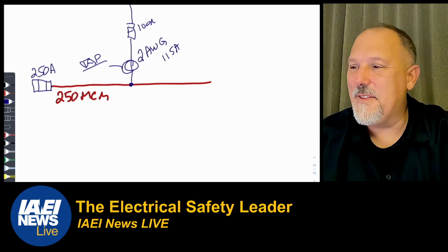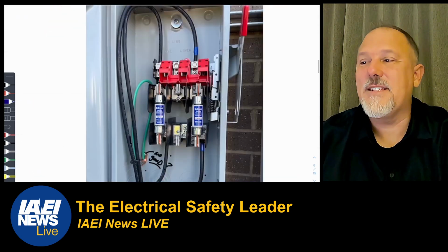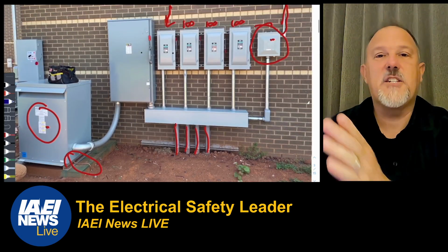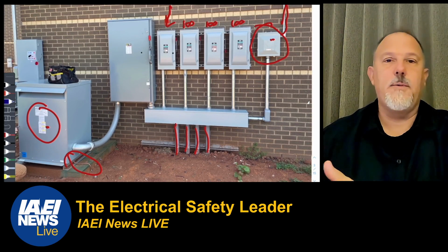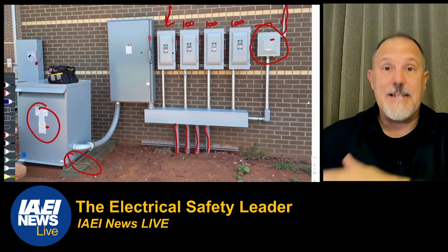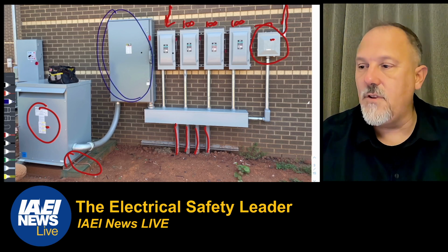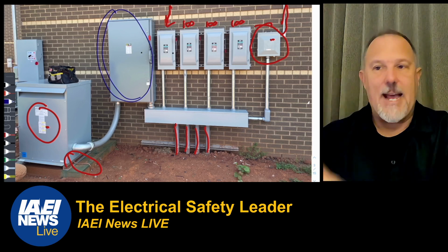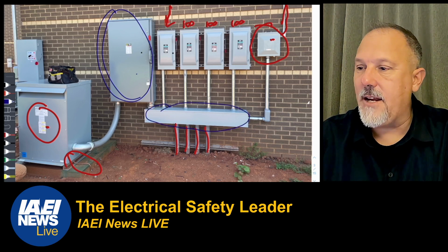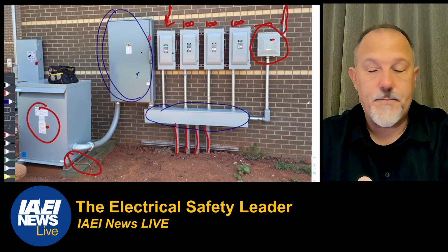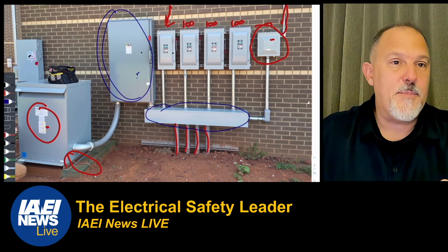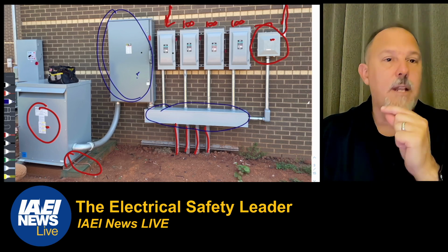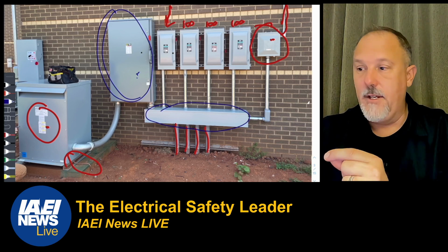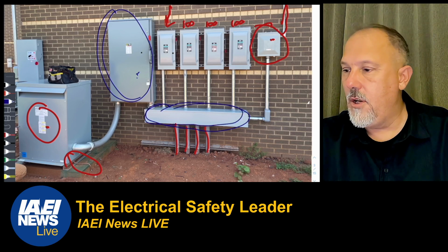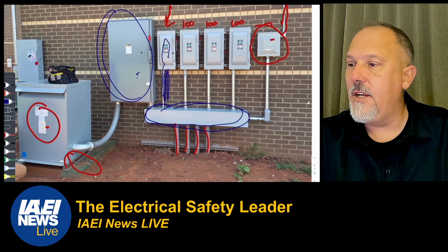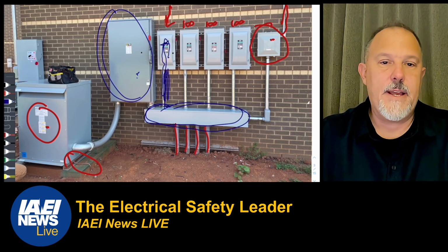So here's another thing that we started talking about, and this is when the pictures came to me. Because when he explained it, I was thinking that secondary conductor was a transformer secondary conductor, and you can't tap a tap. But I've got a fusible switch on the very secondary of this transformer. So I'm not tapping a tap, because the tap is occurring on the secondary of this. I'm tapping a feeder. So then where do we go for feeder taps? We have to understand the tap rules. What's the length of the conductor that I'm permitted to have tapping in on this feeder, going up to this fusible switch, from here to here?